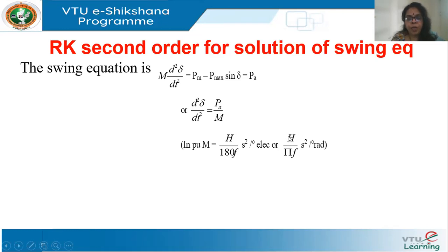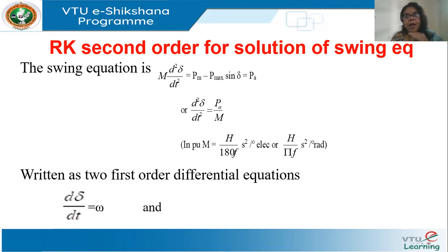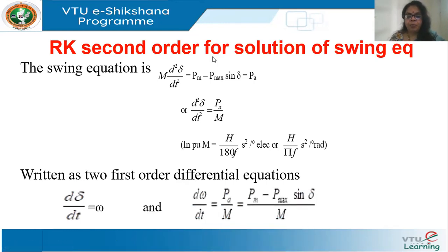I rewrite this equation as d²delta/dt² = Pa/M. And M in per unit, if calculating in electrical degrees, is H/(180F), or if in radians, H/(pi*F), where H is unique to the machine in mega-joules per MVA. I write this as two first-order differential equations: d(delta)/dt = omega, and d(omega)/dt = d²delta/dt² = Pa/M = (Pm - Pmax * sin(delta)) / M.